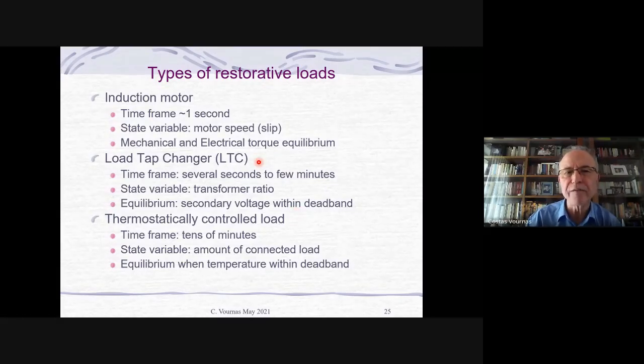If you go to the long-term time scale, then you have slower acting load restoration, and this is done in bulk power system transformers, where you have load tap changers that try to restore the voltage on the distribution side. So if you have loads that are voltage sensitive, then by restoring the voltage at the distribution side, you also restore load power. And these tap changers act with time constants of, let's say, a few seconds, like for instance 5 to 10 seconds. So they are much slower than the generator and motor dynamics. And the equilibrium here is when you have the secondary voltage within the deadband.